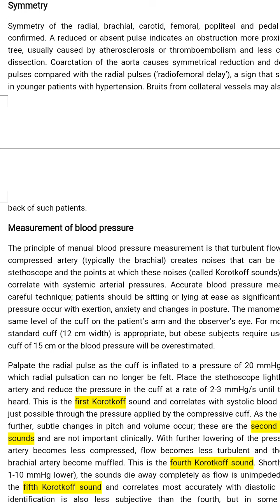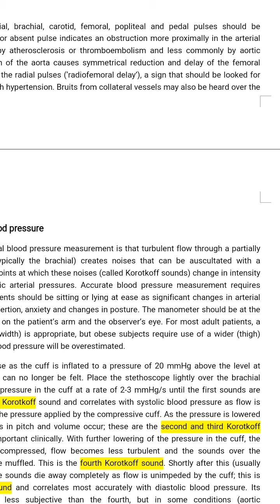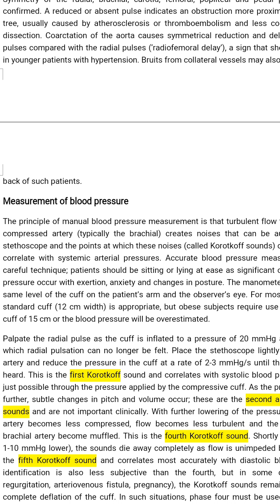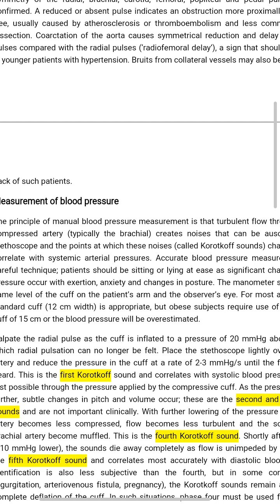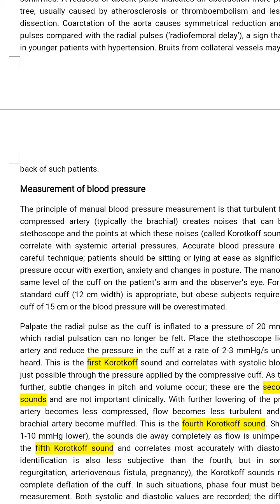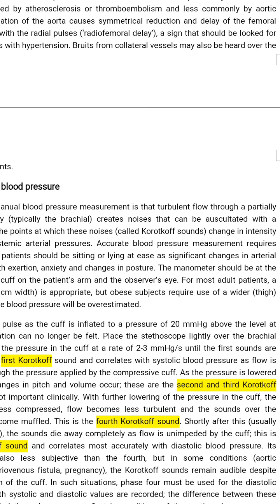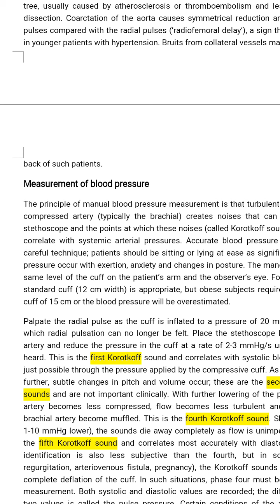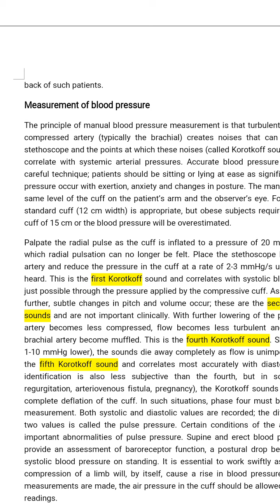The patient should be sitting or lying at ease, as significant changes in arterial pressure occur with exertion, anxiety and change in posture. The manometer should be at the same level as the cuff on the patient's arm and the observer's eye. For most adult patients, a standard cuff 12 centimeters in width is appropriate, but obese subjects require a wider thigh cuff of 15 centimeters, or the blood pressure will be overestimated. Palpate the radial pulse as the cuff is inflated to a pressure of 20 mmHg above the level at which radial pulsation can no longer be felt.